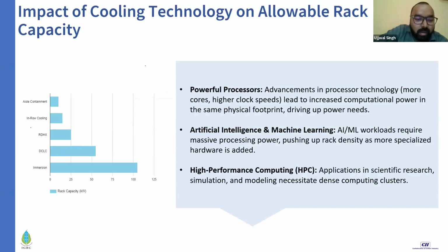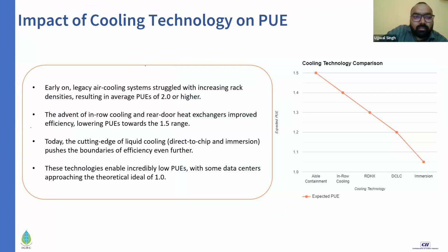And as I said, the rack capacities increase as we go from aisle containment to immersion. As you can typically see, whatever we have discussed till now, the rear door heat exchanger goes up to 25, and from immersion you can even achieve more than 100 kilowatts. From the PUE perspective, though it is not a hard and fast rule, with aisle containment I have seen 1.3 also getting achieved. It depends on a lot of other things, but to generalize, from aisle containment to liquid immersion cooling, you can reduce from 1.5 to even 1.03, as I said, to be the lowest.